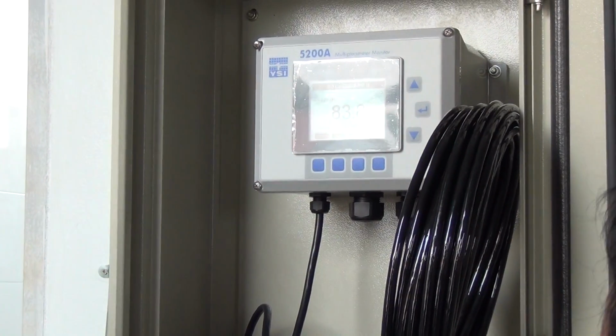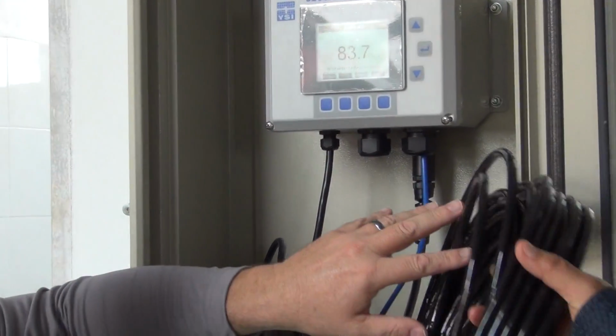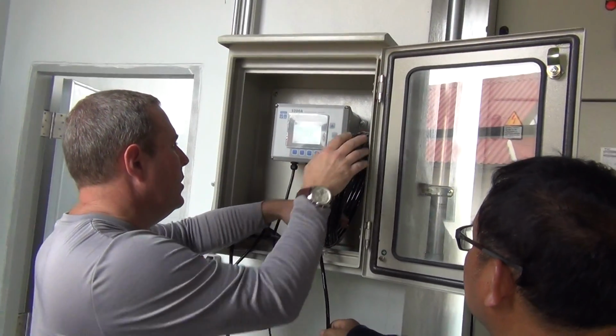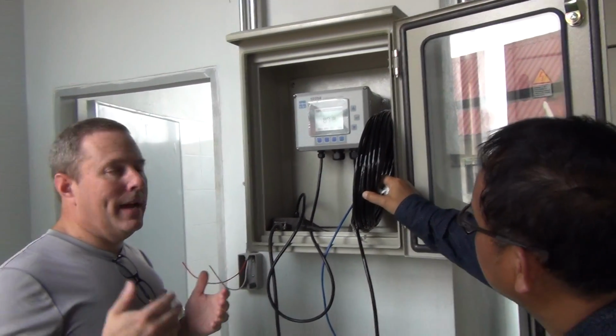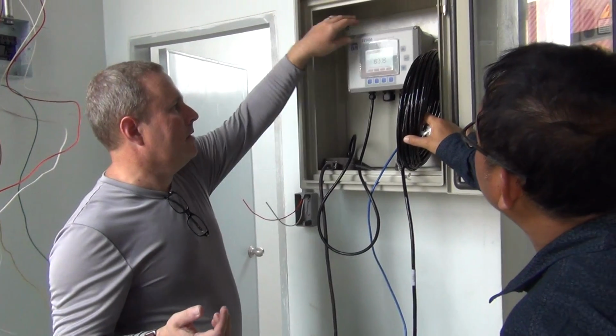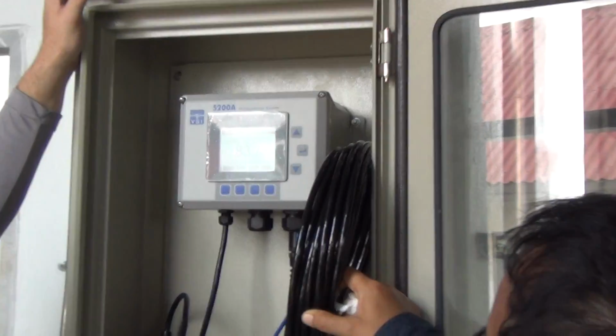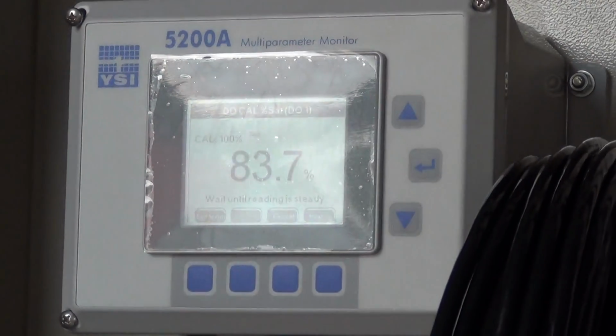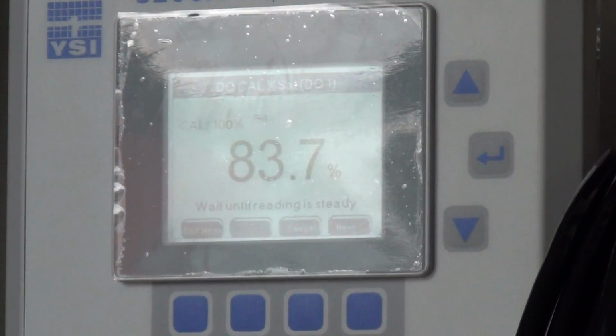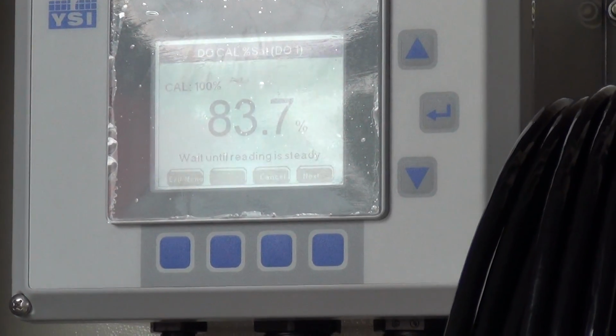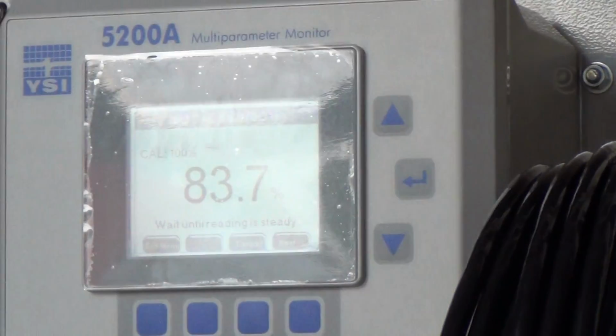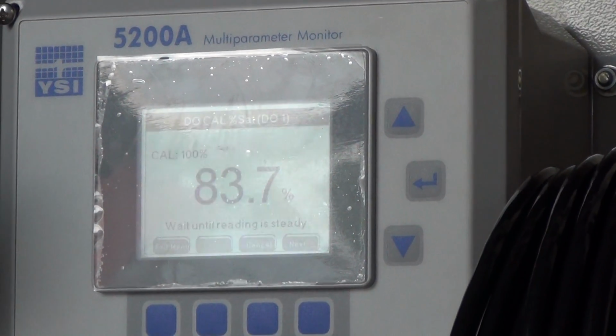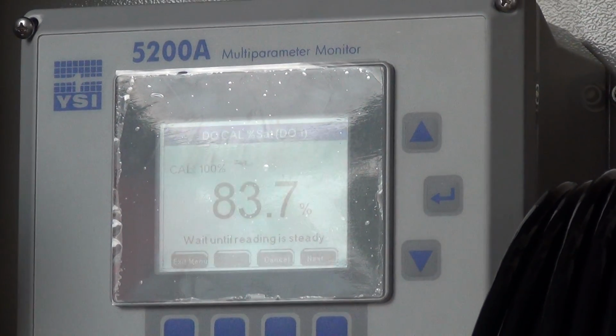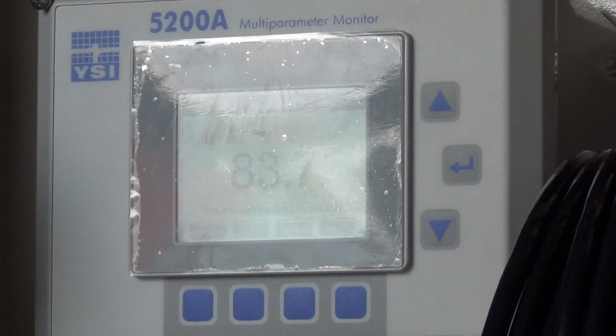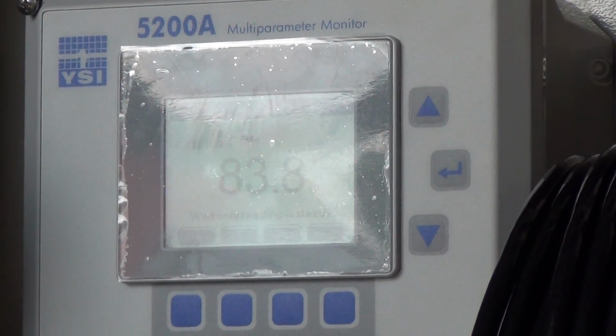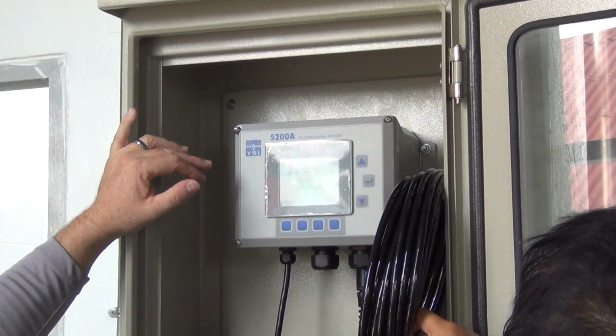It says wait until reading is steady. What that means is this number does not change for at least 30 seconds. Okay? So we have to count it off. And it just changed. So 30, 29, 28, changed. So we start again. 30, 29. Actually, you could feel the wind blow and it probably did that. 25, 24, 23... 5, 4, 3. It changed. And we do it again. It takes a little bit of time.